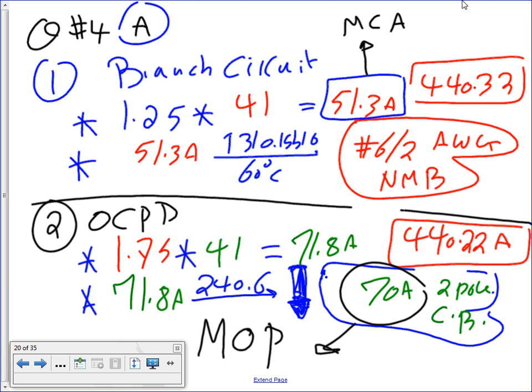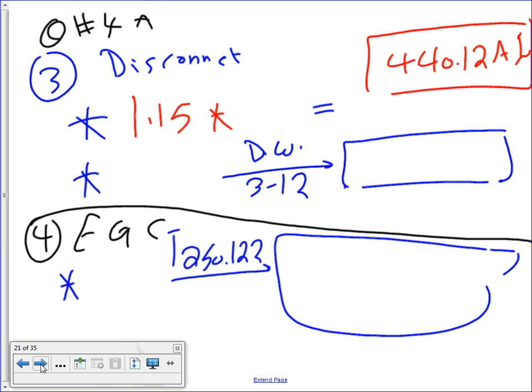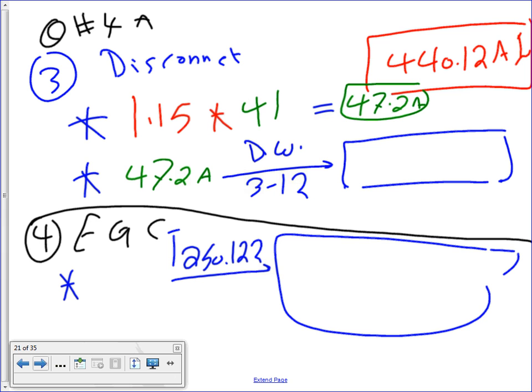Number 2. Can I move to number 3, please? Yes. Okay. Number 3 is your disconnect. You're going to take the 41 amps, same thing, 1.15. What's your reference? 440.12a. That's where you get your reference. You got yourself 47.2 amps. Then you take the 47.2 amps, same thing. That will get you a healthy 60 amp, two-pole, non-fused disconnect. 60 amp, two-pole, non-fused disconnect.